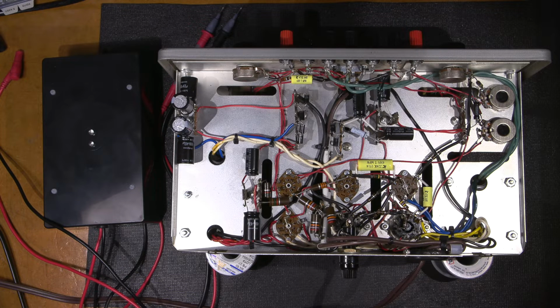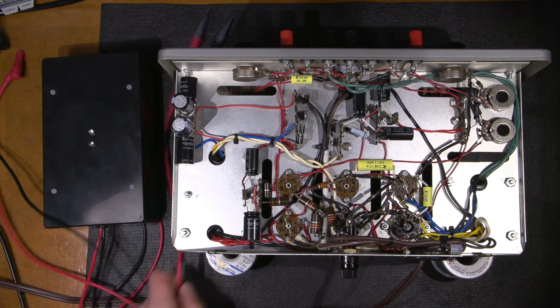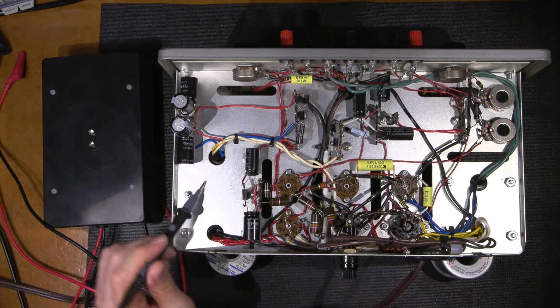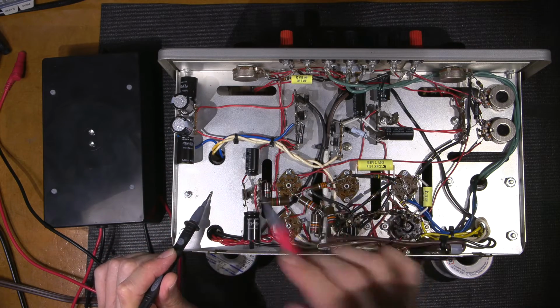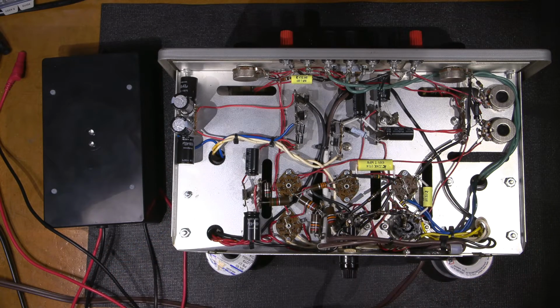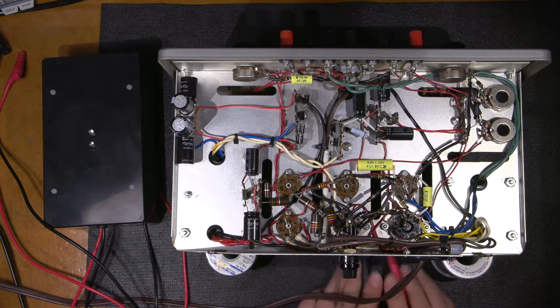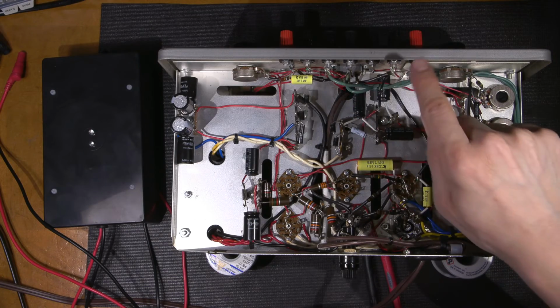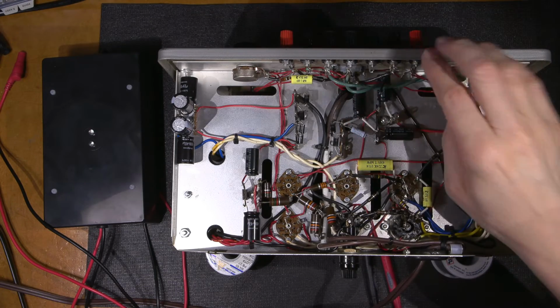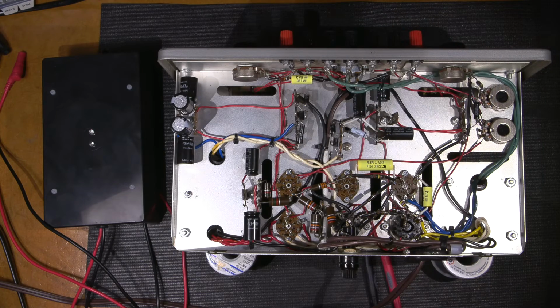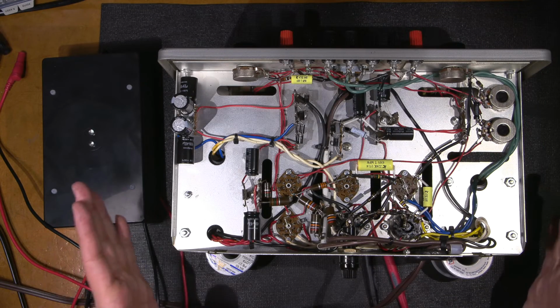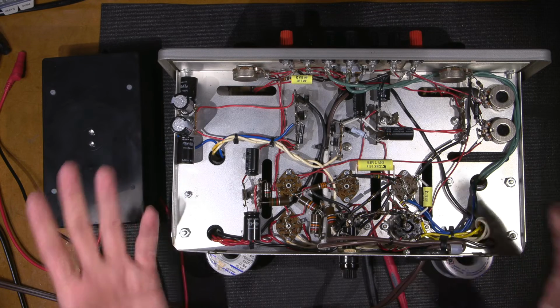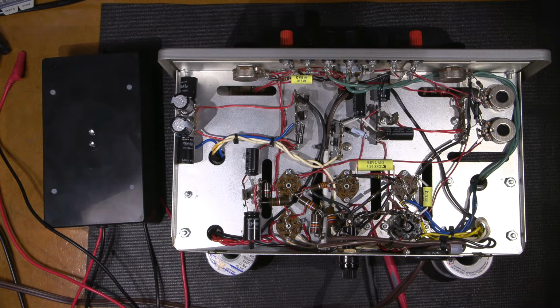Very, very important. Now, another thing that will get a lot of techs zapped is they think that taking their discharging device and attaching one probe to the chassis and going around touching all the capacitor leads is going to make sure that all the capacitors are discharged. Very, very false. In this unit here, on the front, there's supposed to be basically a bridge bar that connects the chassis to the negative in this entire system. So really, the chassis right now is completely isolated. There is no bridge bar or anything, and that can fool a lot of people.